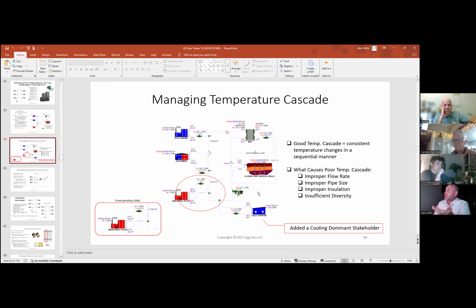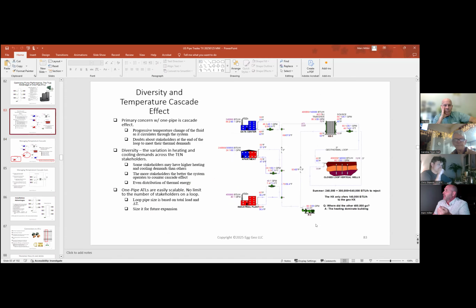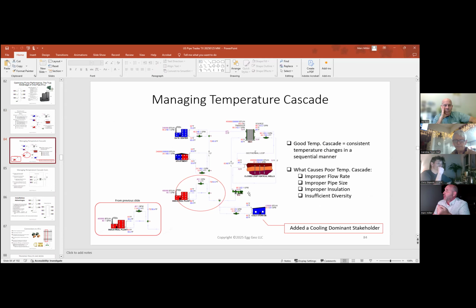Now, what causes poor temperature cascade? Improper flow rate. As we've shown in this example between these two, the pump sped up from 28 GPM to 52. Improper sizing of the pipe? Well, the design software automatically takes care of that. I've just shown that we can add another stakeholder to this system and we won't have to change the pipe size. So as you add residences or other stakeholders onto your thermal energy network, you're not having to go back and dig the street up.